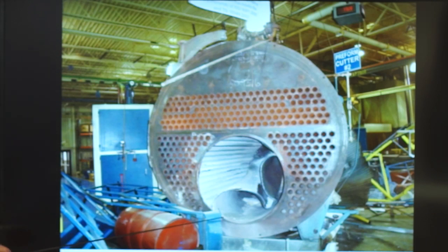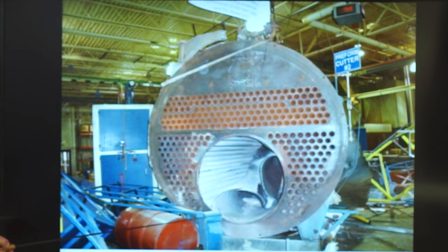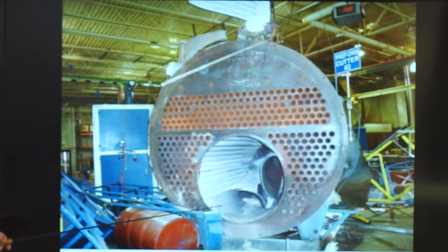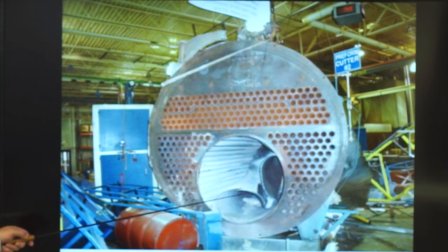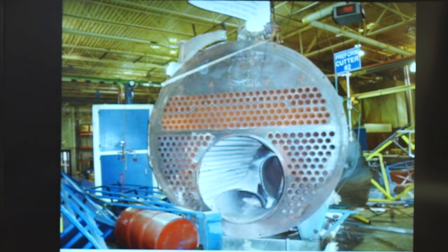The inside of the Morison tube — these are the tubes. The steel covered those tubes, and the violence of the incident caused that steel to buckle and curl. That steel is probably a quarter inch thick, so there's a lot of energy to cause that.